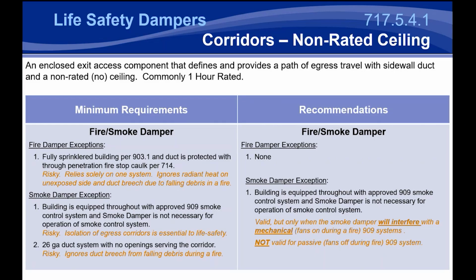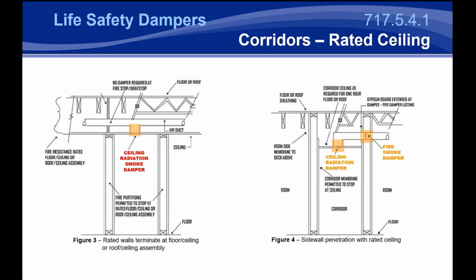Now, if that 26 gauge duct system has no opening serving the corridor, basically your smoke compartment resides within that corridor and you don't have any breaches of that smoke compartment. So there's less of a risk of smoke for the damper to be in that place. We think it's a little bit risky when you're dealing with corridors specifically, because corridors are a means of egress out of the building. So we think it's best to protect that as best as possible with your fire smoke damper. But if it is going to interfere with that smoke control system, you can certainly remove it there. And I've certainly seen many engineers remove that damper if there are no openings serving that corridor.